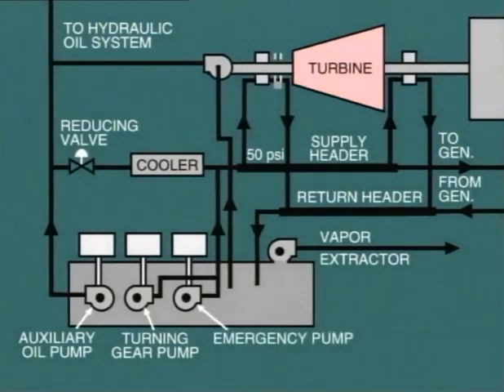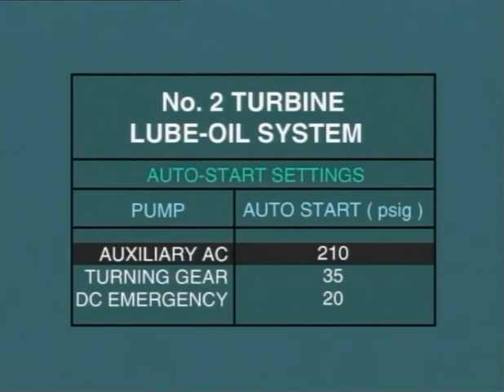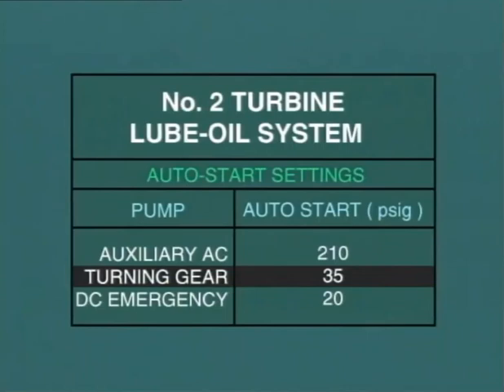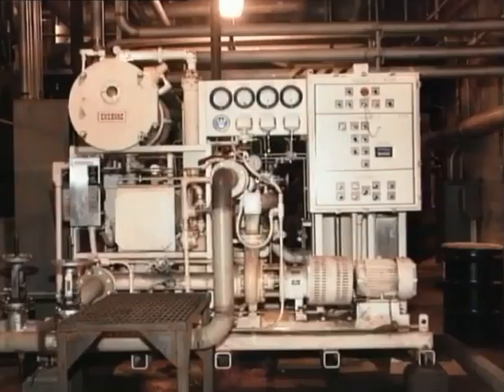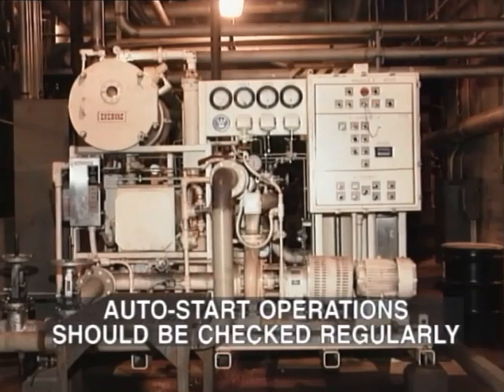There is also a DC emergency pump which will provide lubrication in the case that all AC service supply power is lost. So we can see that there is, in fact, a hierarchy of oil pumps with automatic start-up based on pressure readings. If the high-pressure oil pump fails and the pressure falls, the AC auxiliary oil pump will cut in automatically. If the lube oil pressure falls, the turning gear oil pump starts up automatically, and if this consequently fails, the DC oil pump will start. The pump auto-start operations should be checked on all pumps regularly.